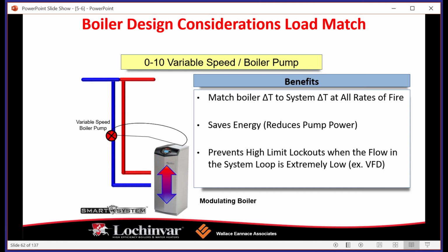What we want to do, and what we do actually achieve, is we're going to turn the boiler on. It's going to begin to heat the water, and then based on information that the boiler is reading on its inlet and outlet temperatures, it's going to say, you know what, I have a set point of 140 degrees. The outlet temperature is at 125 degrees. Our return water is starting to heat up a little bit, and what it's going to do is modulate the fire rate.